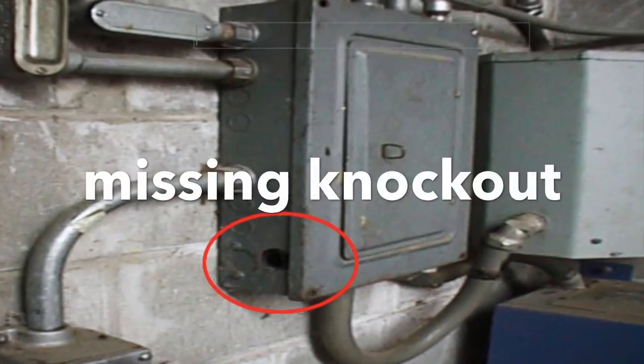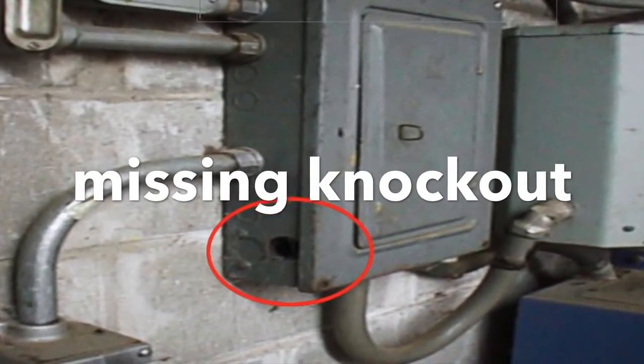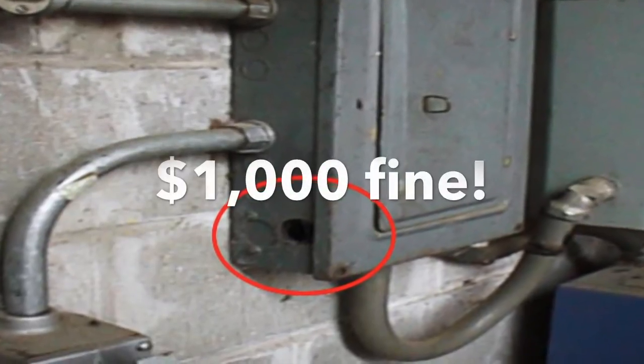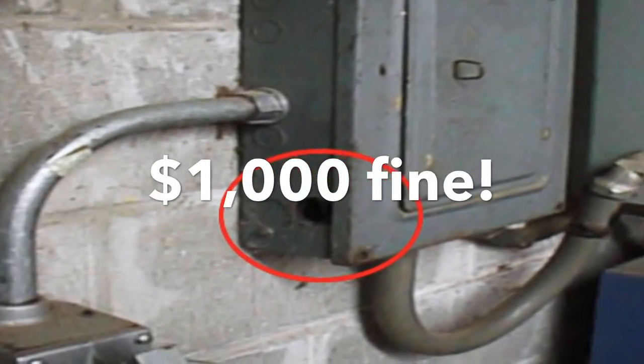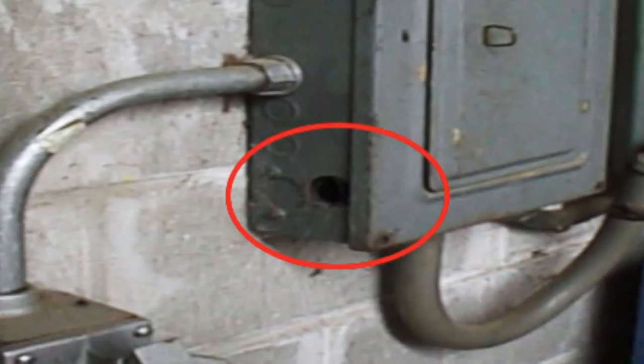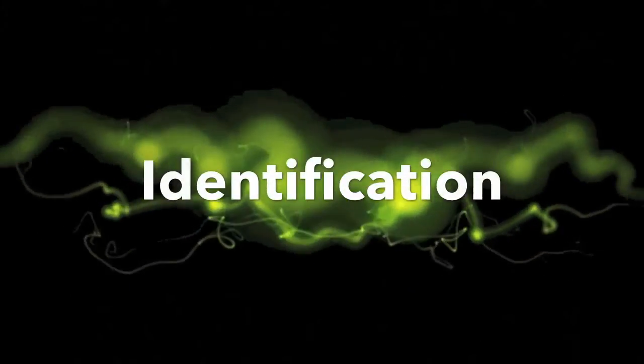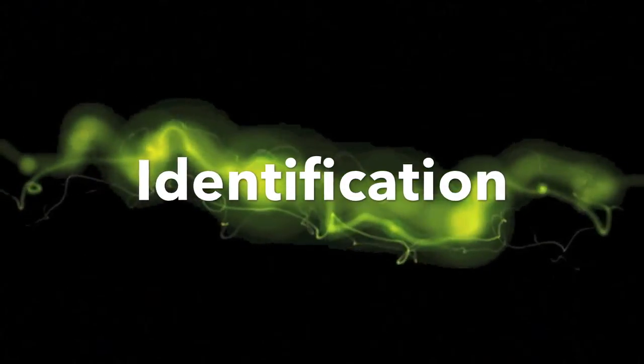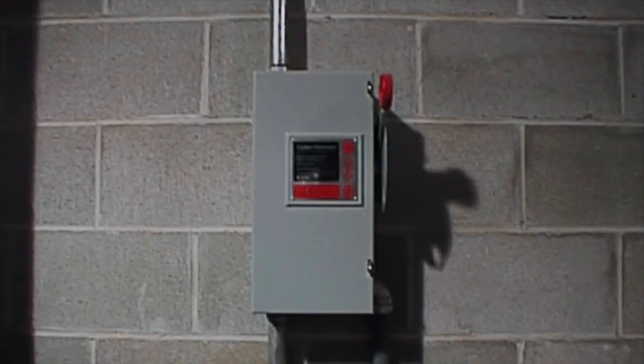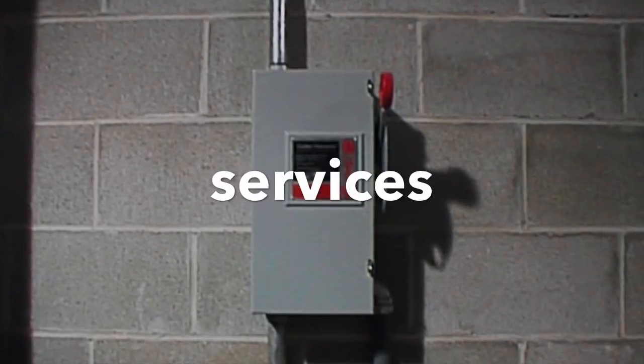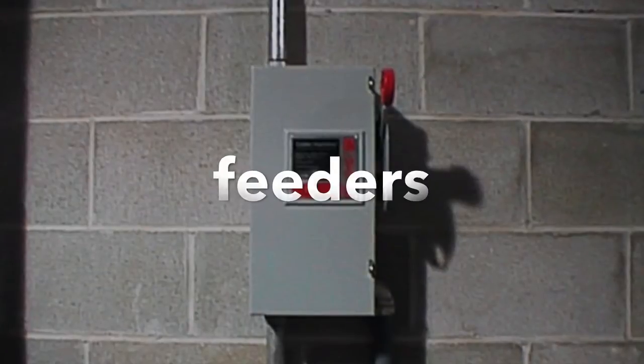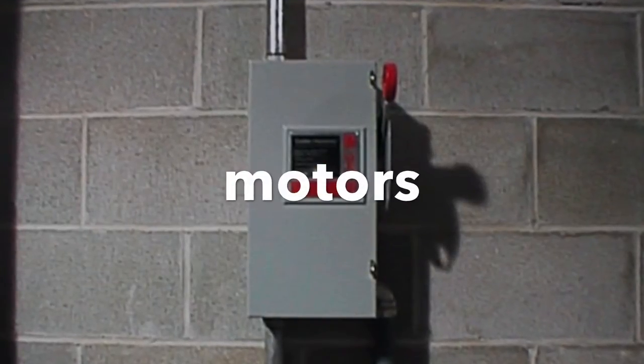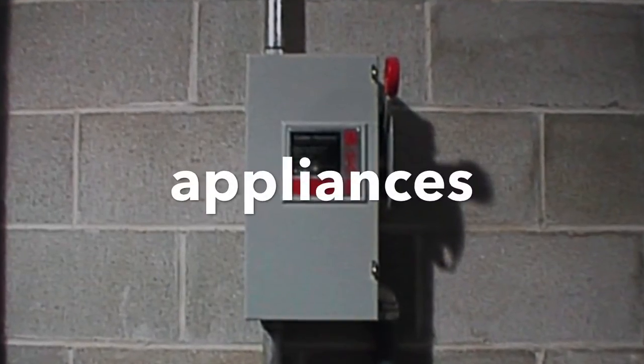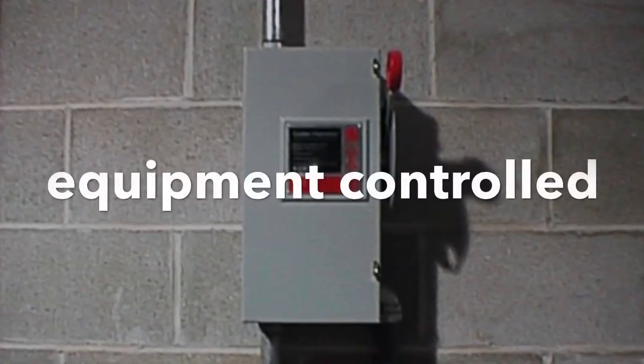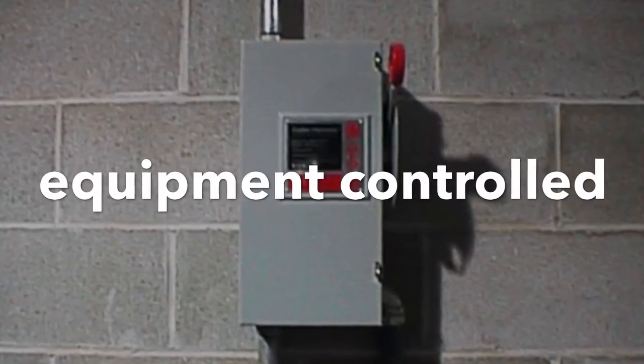This box has a missing knockout. This missing knockout alone has the potential fine of $1,000. Each disconnect, circuit breaker, or other overcurrent device must be marked. It will be marked with information such as services, feeders, branch circuits, motors, or appliances. The marking must be durable. This device must be labeled or marked with the equipment name that it controls.